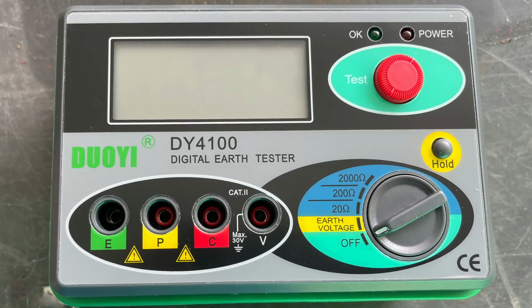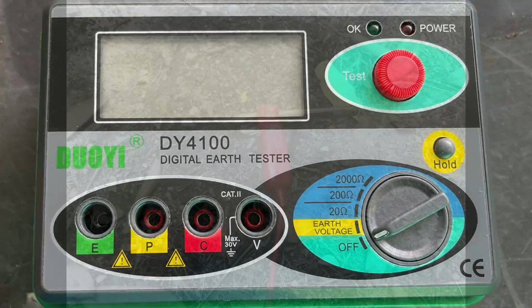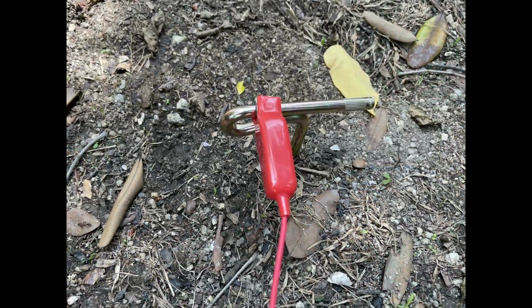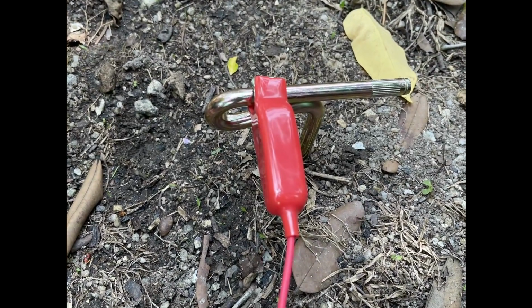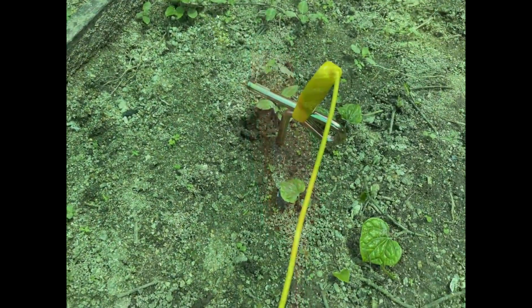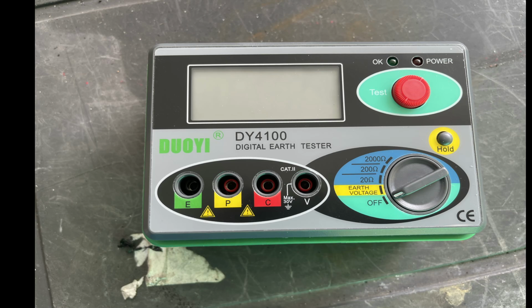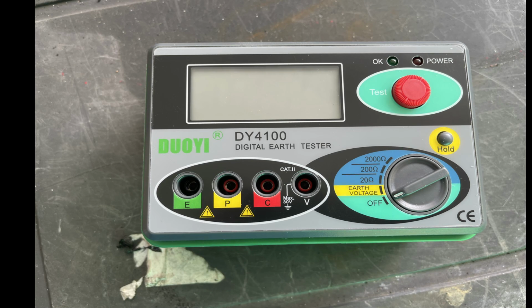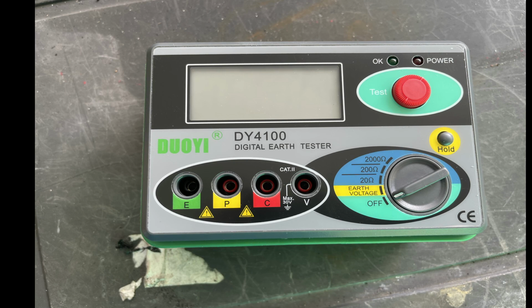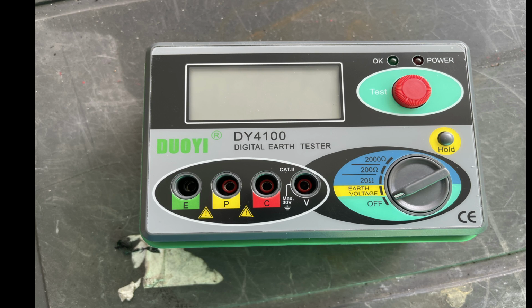I use a digital earth resistance soil resistivity tester meter which consists of 3 probes with spikes, with 3 long wires colored red, yellow and green. A digital earth resistance soil resistivity tester meter is an instrument used to measure the resistance of the earth electrode and soil resistivity. It works on the principle of injecting a current into the soil through the earth electrode, and then measuring the voltage drop across the electrodes to determine the resistance.